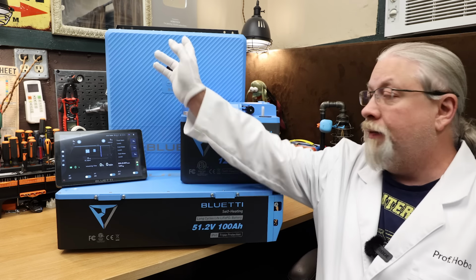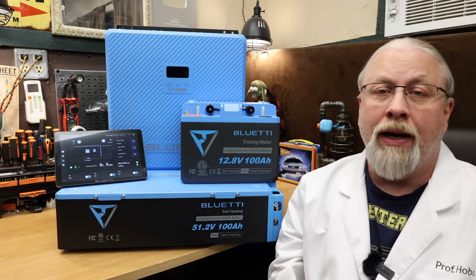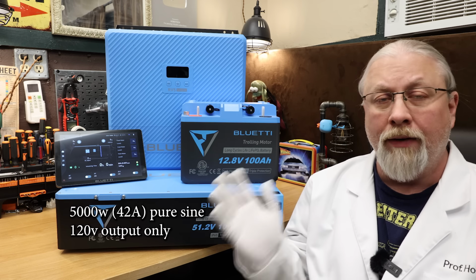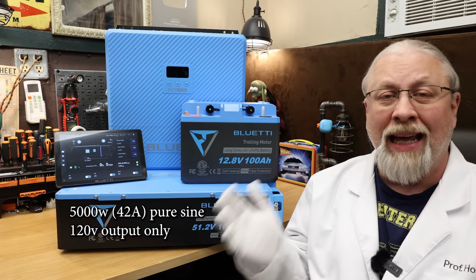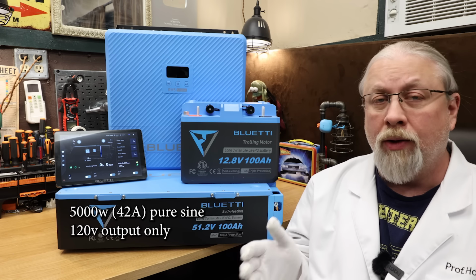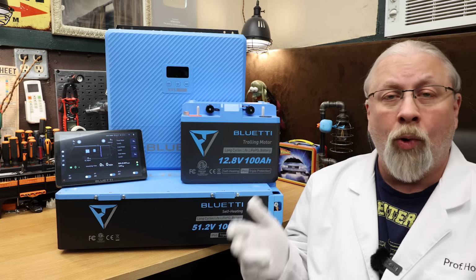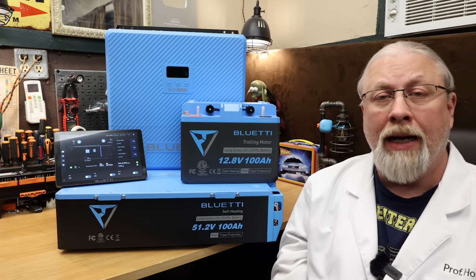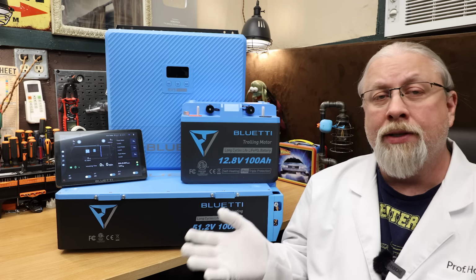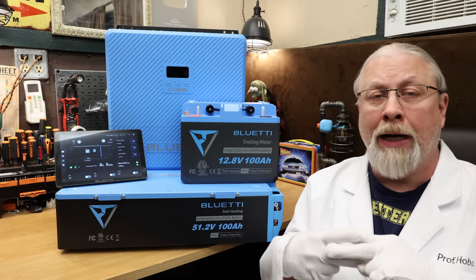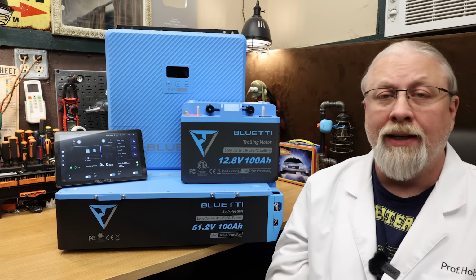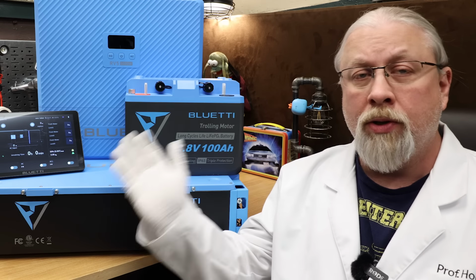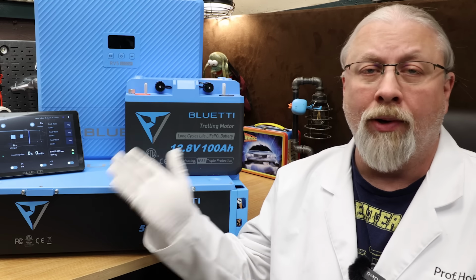Now, as for the RV5 Power Hub, as they call it, it's rated at 5,000 watts, both for inverting and battery charging. It can be AC charged with either 120 or 240 volt split AC, or from a level 2 EV charger per the manual. The inverter, however, only outputs 120 volts. There is no parallel option to output 240 volt split. I'll say that again, there is no 240 volt split phase output support on this product.